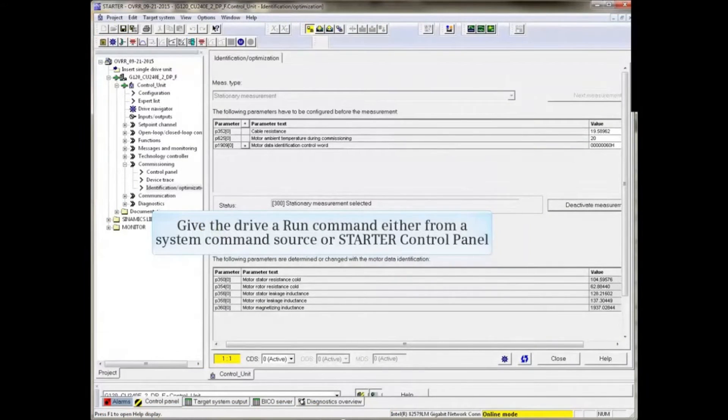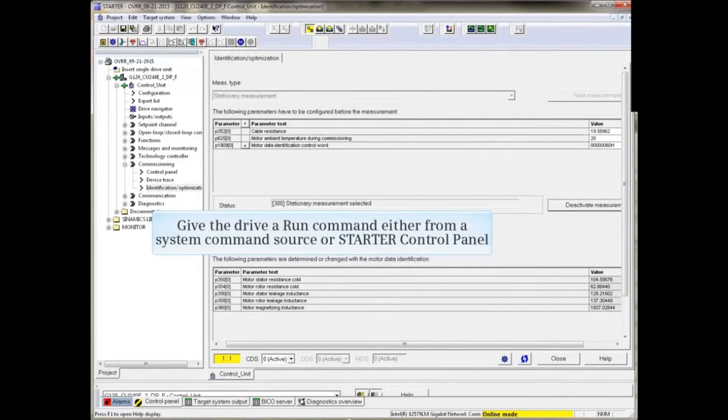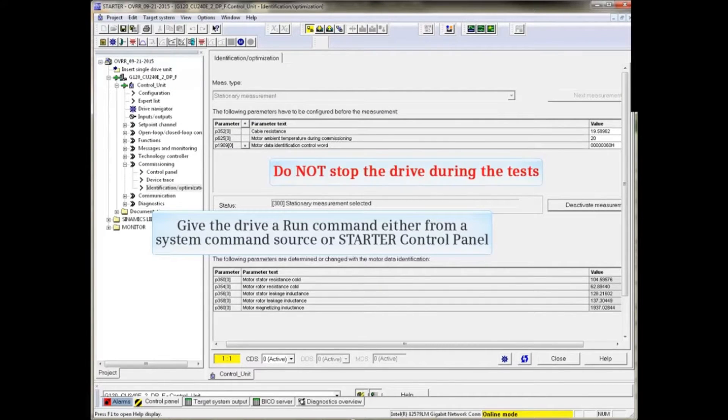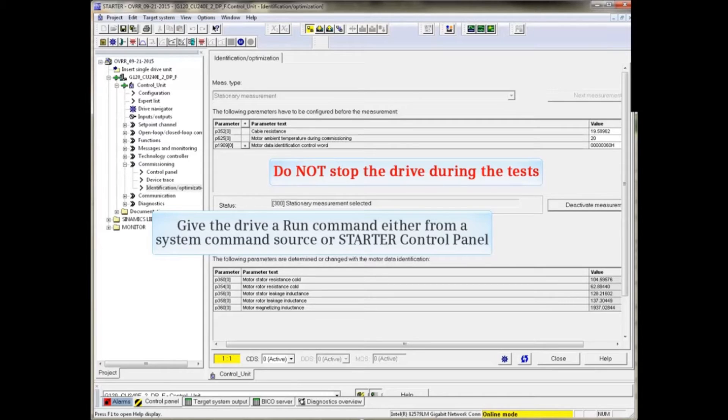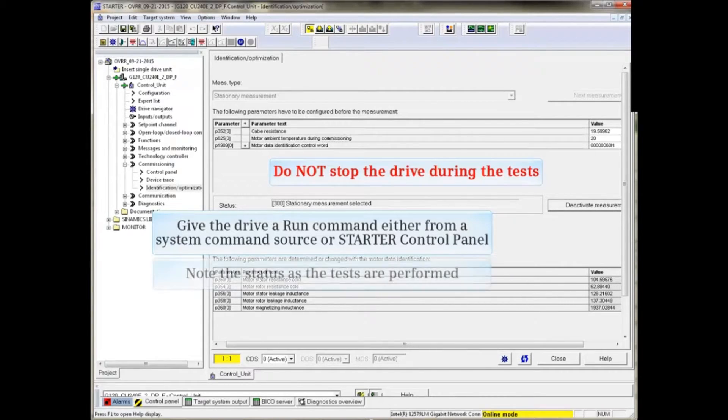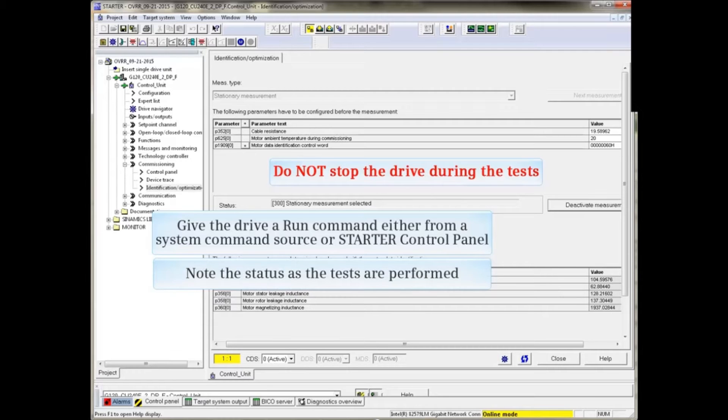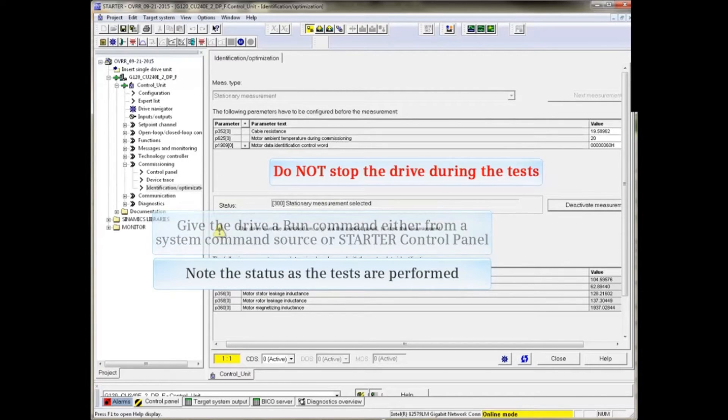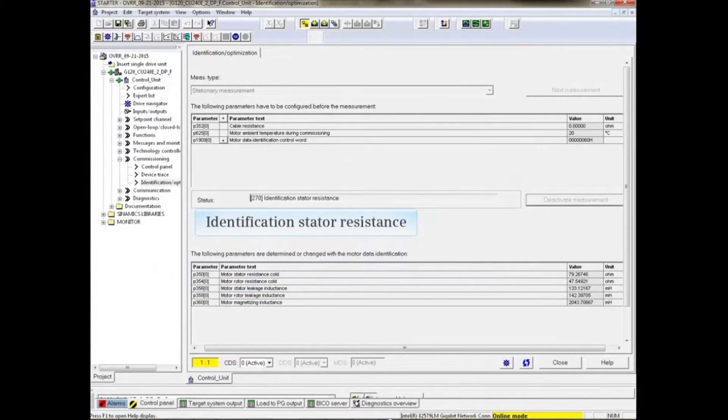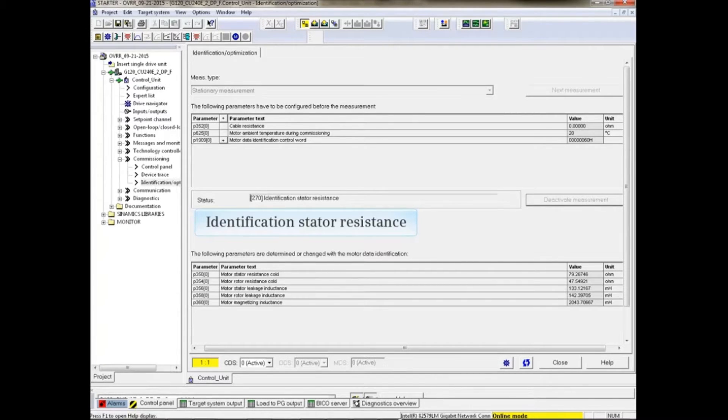Give the drive a run command either from a system command source or starter control panel. Do not stop the drive while the tests are being performed. The drive will stop automatically when the process is complete. Note the status identifiers as the identification routine is performed.